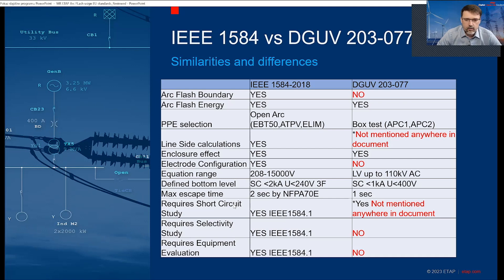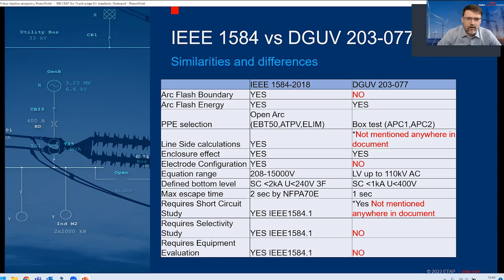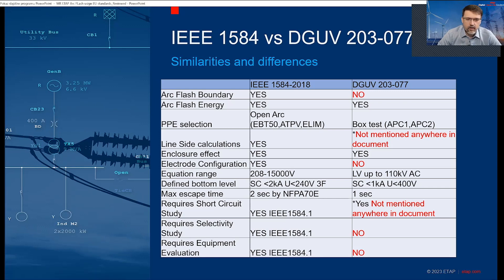Is a short circuit study required? Yes — for IEEE 1584, and for DGUV it's not specifically mentioned but we obviously need short circuit current values to calculate anything. There are no requirements for selectivity or equipment evaluation, but those aren't necessarily the focus of the standard — they're more part of the design process.